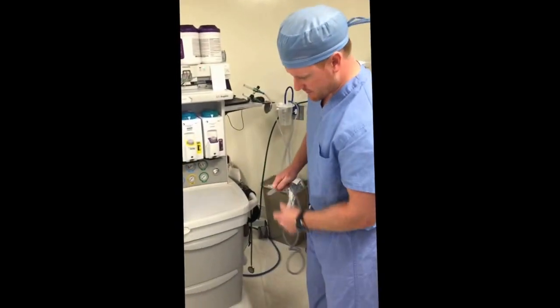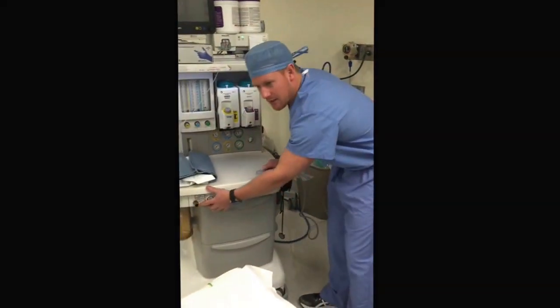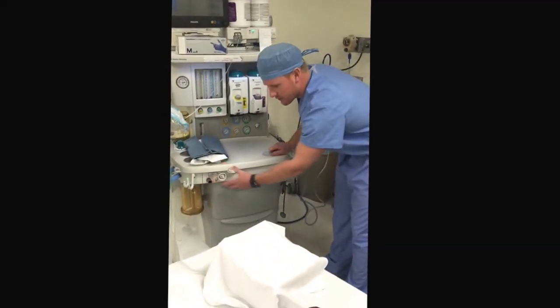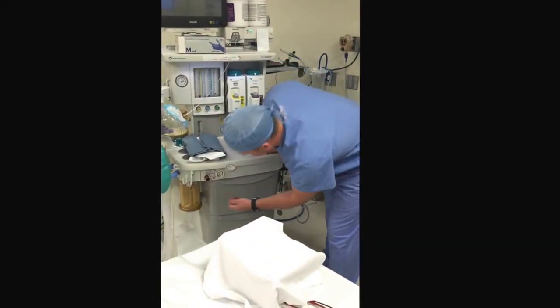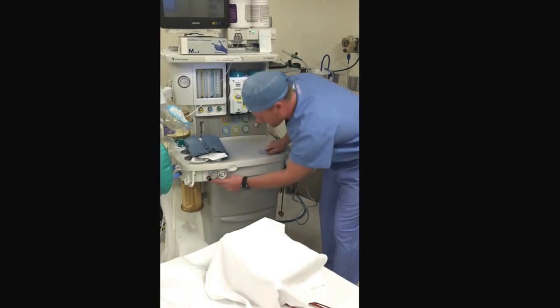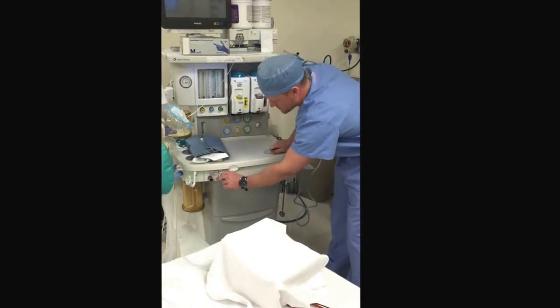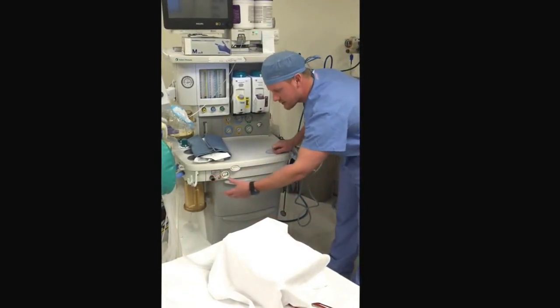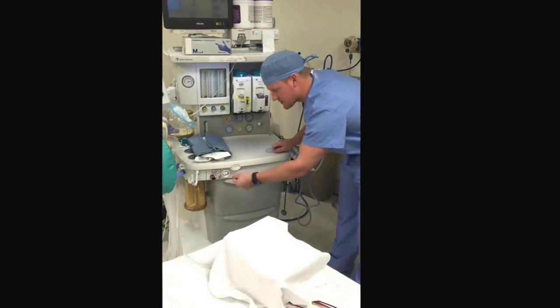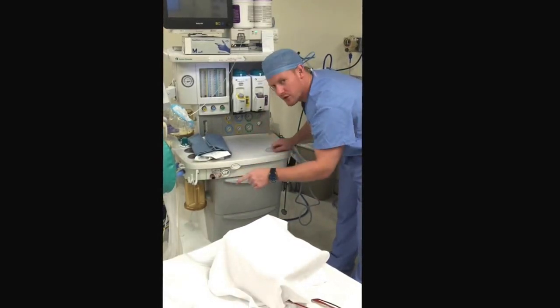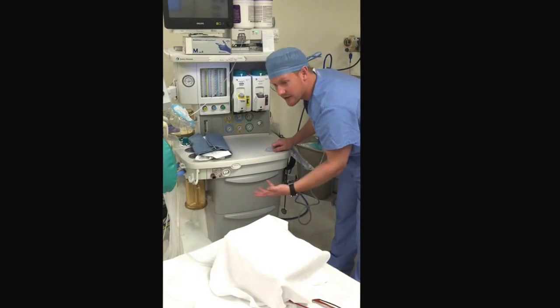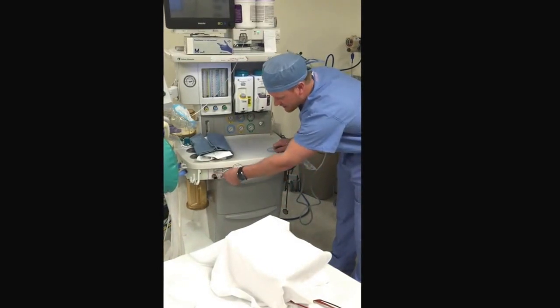The next part is we would check the low pressure system. The way you check the low pressure system is at the common gas outlet, and we don't have the bulb to show you, but you would switch from the machine to the common gas outlet and attach the bulb, squeeze it until it's flat, and make sure that no pressure is leaking within that system. Like I said, we don't have the bulb. So I'm going to switch back to the machine.